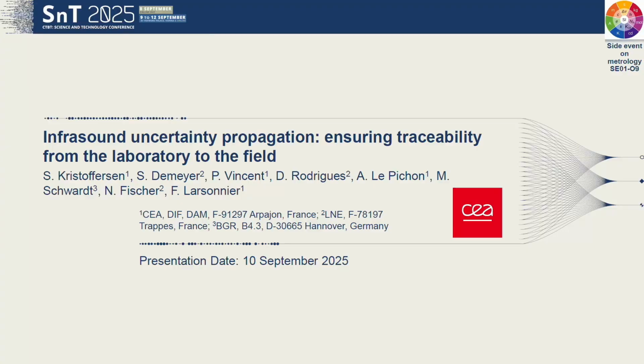Okay, thanks for the introduction. So like Richard said, I'm going to be talking about infrasound uncertainty propagation, so ensuring traceability from the laboratory and primary calibrations to the field. And this was done as part of the Infra AUV project, which was a project on metrology for low frequency sound and vibration. And my contributions were in working with incorporating these on-site calibration methods into the full measurement traceability.